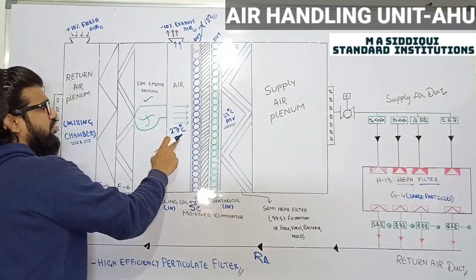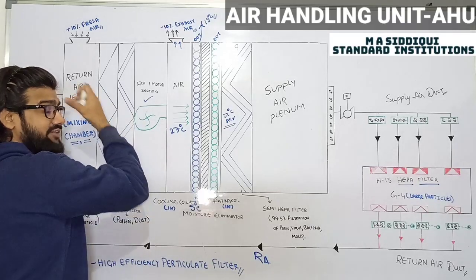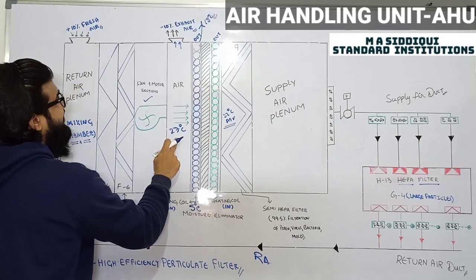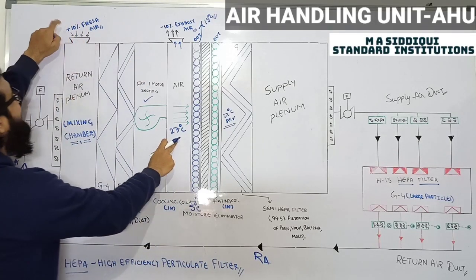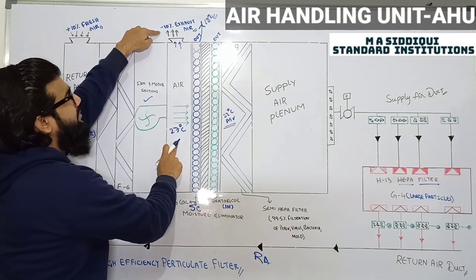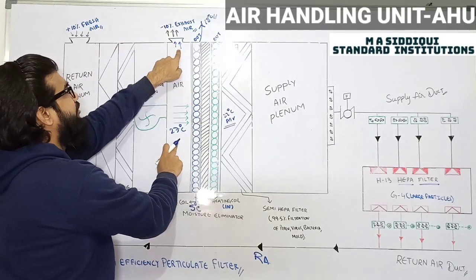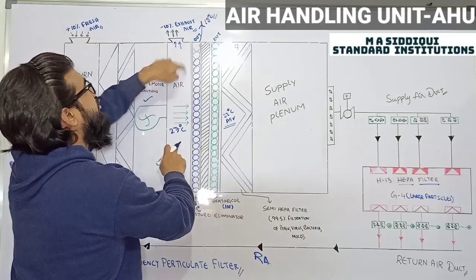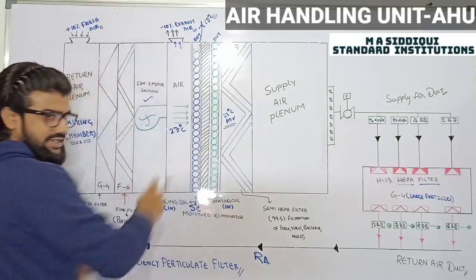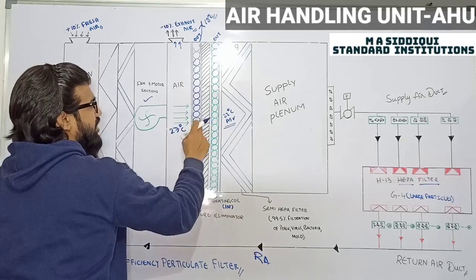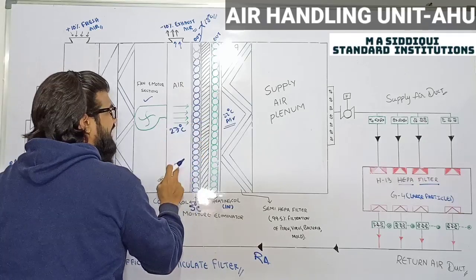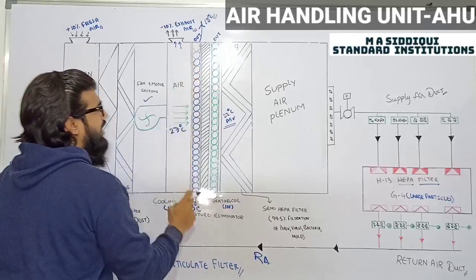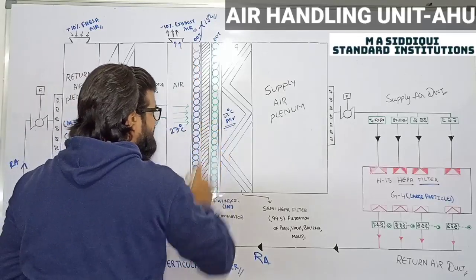Okay, initially the temperature of my mixed air, that is of fresh air and return air, was 27 degrees Celsius. From here, as I have added 10% fresh air, 10% exhaust has been removed with the help of an opening with a damper. Opening with a damper for fresh air, opening with a damper for 10% exhaust of air. Understanding? And this air is striking the cooling coil, and from that my air temperature is being controlled by the cooling coil from 27 degrees Celsius to 22 degrees Celsius.